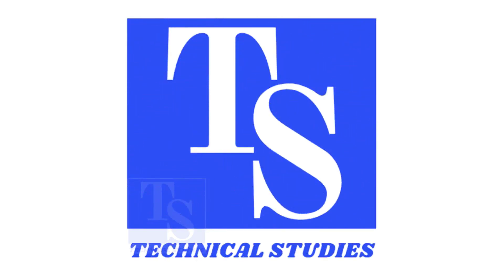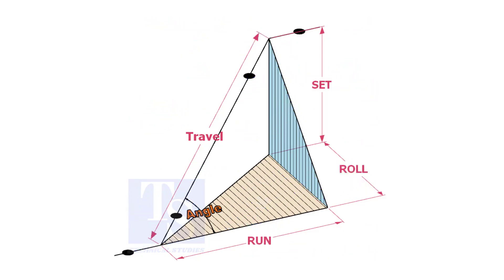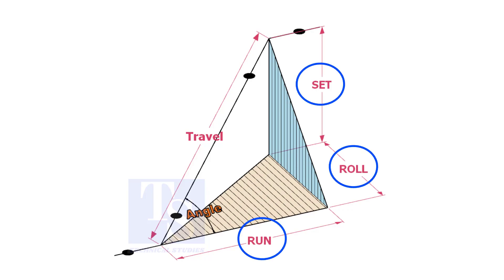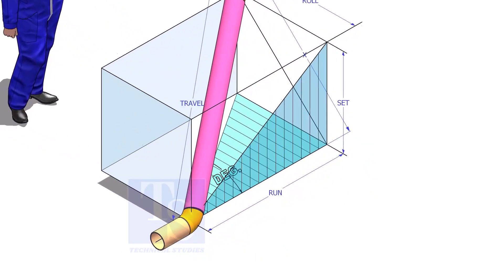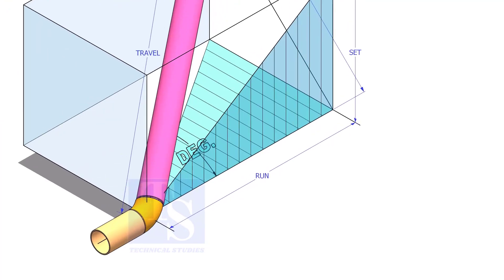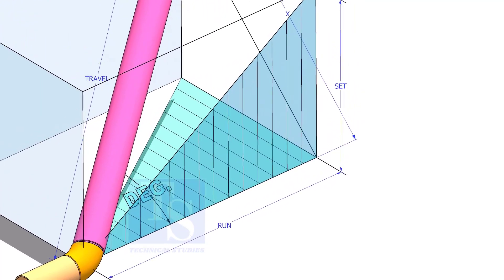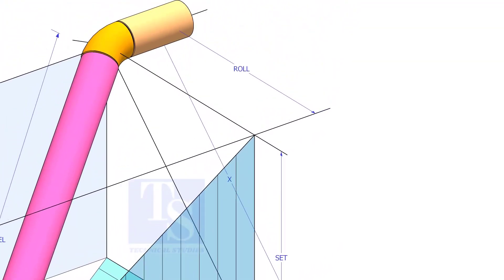Welcome to Technical Studies. In a piping drawing of a double rolled offset, usually the dimensions of the run, set and roll are given. In this video, I will show you how to calculate the travel length and the including angle of a double rolled offset pipe.